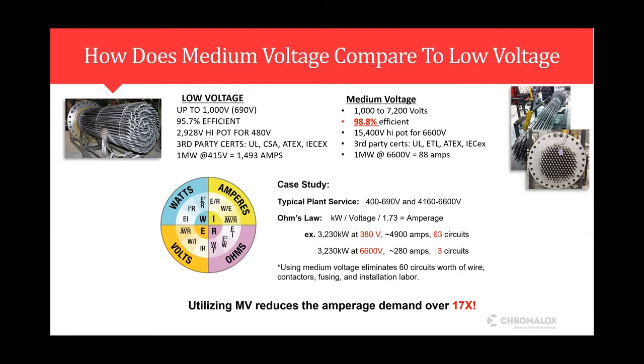So the big takeaway on medium voltage that I'd like for everybody to have is that using medium voltage reduces the amperage demand. In the case study here, in an example at 380 volt at 3,230 kW, at three phase, that's 4,900 amps. That's a total of 63 circuits if the customer wants to use 380 volt, as opposed to our direct connect technology at 6,600 volts. You're going to be drawing 280 amps, and that's only 3 circuits. So using medium voltage eliminates 60 circuits worth of wire, contactors, fusing, and installation labor. This is a huge savings when comparing low voltage to medium voltage.